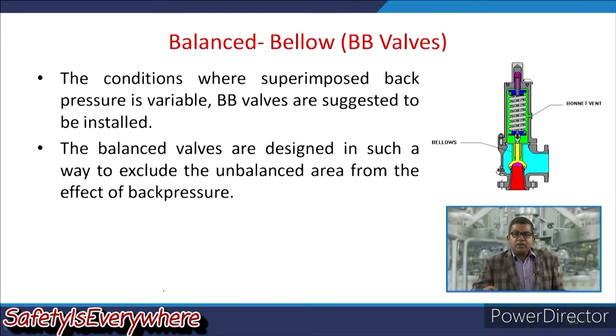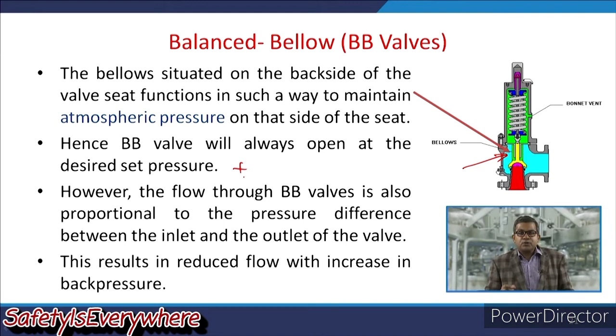Bellows situated on the back side of the valve seat function in such a way to maintain atmospheric pressure on the side of the seat. Hence the balanced bellow valve will always open at the desired set pressure. This is the plus point of this valve. However, the flow through a balanced bellow valve is also proportional to the pressure difference between the inlet and outlet of the valve. So this results in reduced flow with increase in back pressure.